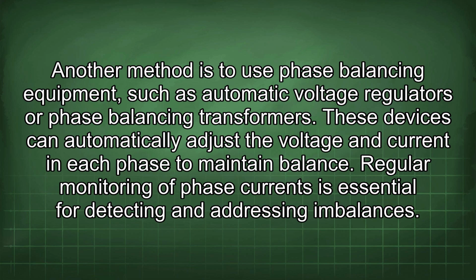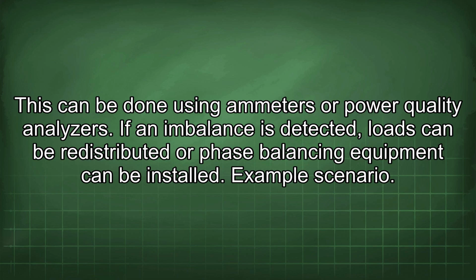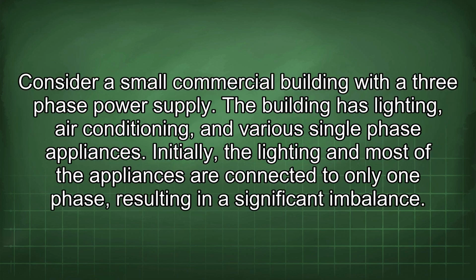Regular monitoring of phase currents is essential for detecting and addressing imbalances. This can be done using ammeters or power quality analyzers. If an imbalance is detected, loads can be redistributed or phase balancing equipment can be installed. Example scenario. Consider a small commercial building with a three-phase power supply. The building has lighting, air conditioning, and various single-phase appliances.